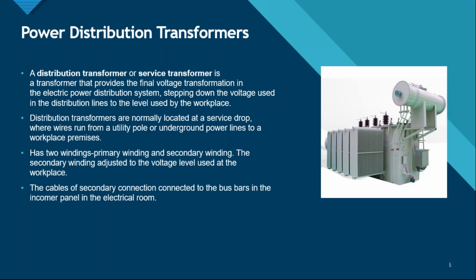Distribution transformers are normally located at a service drop, right? Wherever your local electricity service, like for Qatar, you can say Kahramaa, right, is supplying the electricity. Wherever there is a service drop, you can locate a transformer, a step down transformer to be particular, that might be stepping down the voltage for your industrial use, right? Where wires run from a utility pole or underground power lines to a workplace premises. Any transformer has two windings, right? It has a primary winding and a secondary winding. For a step down transformer, the primary winding might be more in size than the secondary winding, right? Depending on the ratio, depending on the voltage rating. The secondary winding can be adjusted. There are taps in the transformer, so depending on your requirements, you can adjust the secondary winding to the voltage level that you want to use in your industry, in your workplace.